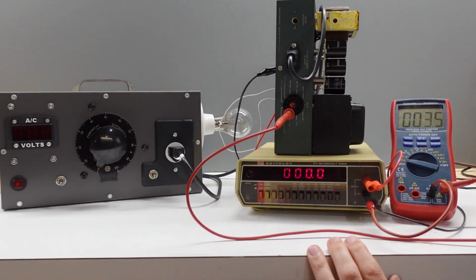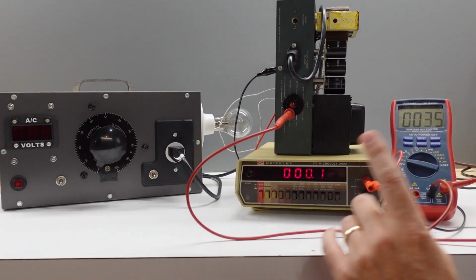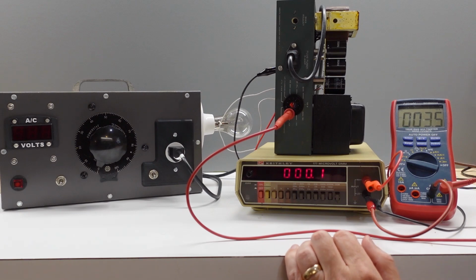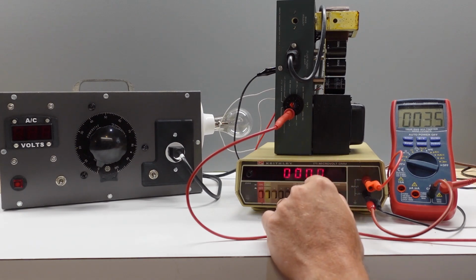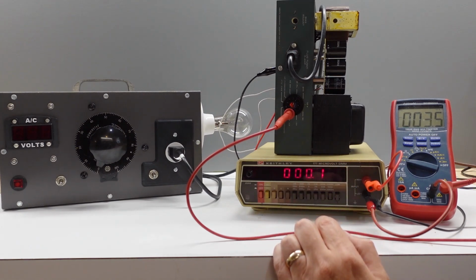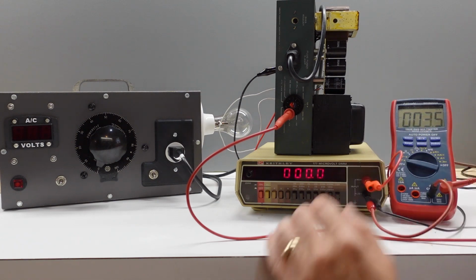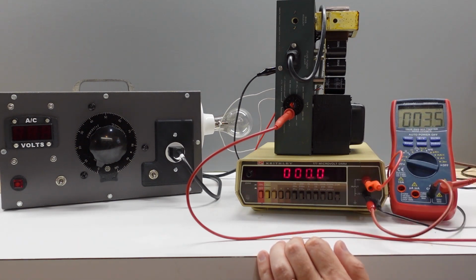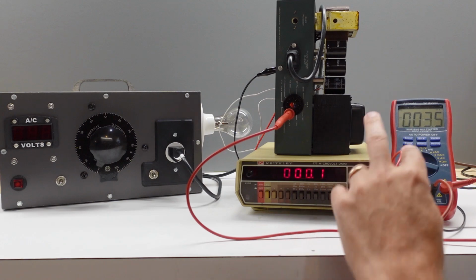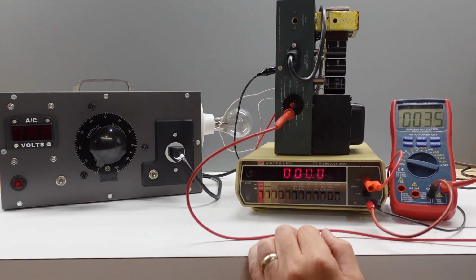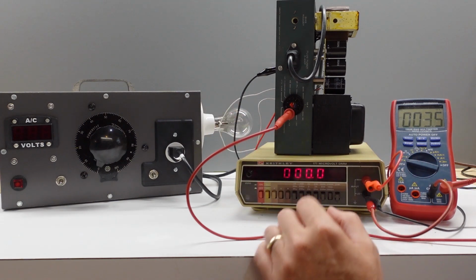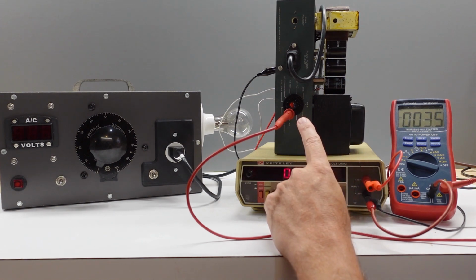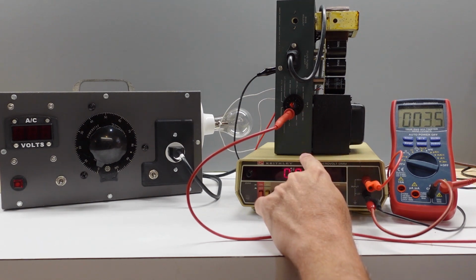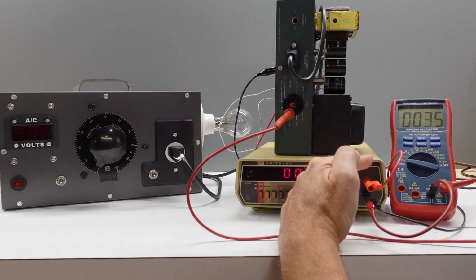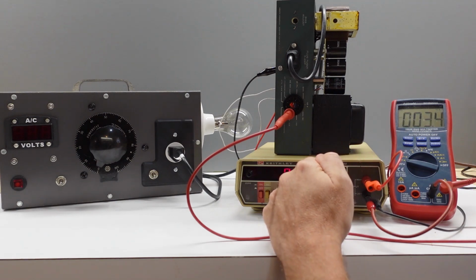So I've also got 2 DC meters hooked up. First is my Keithley, connected to the high voltage output. And I've got my basic DMM here connected to the medium voltage output. So those two, when I get to full line voltage, should read about 800 volts, give or take, on the high voltage side, and about 300 volts on the medium voltage side.